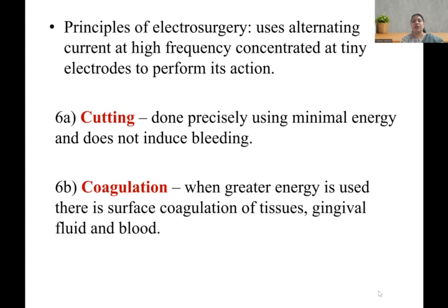It uses alternating current at high frequency concentrated at tiny electrodes to perform its action. First is cutting. It is done precisely using minimal energy and does not induce bleeding. Second is coagulation, where it uses greater energy and there is surface coagulation of tissues, gingival fluid, and blood.